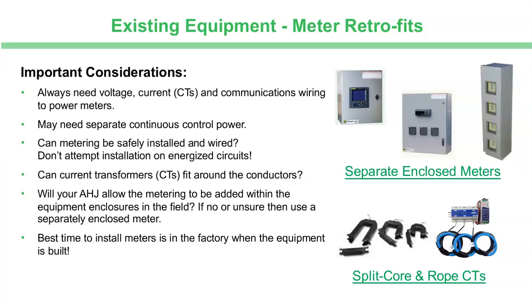One thing that I have found over the years, 32 years plus, is you have to be very aware of what your authorities having jurisdiction will allow you to install in different equipment. And in some jurisdictions, they may require a separate enclosure for the meter rather than it being retrofit in the field into power equipment. Again, new equipment, it can leave the plant, it's got a UL label, and usually that goes very, very smooth. When you're retrofitting, they may be requiring, in some cases, that equipment be refield certified by UL, and that can be very costly and something to avoid. And again, seeing the separate enclosures that we show up on the top right-hand side, it's industry available, so that might be a smart approach whenever that comes up.